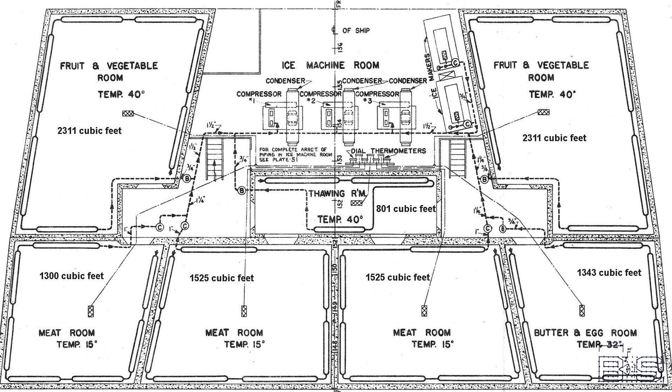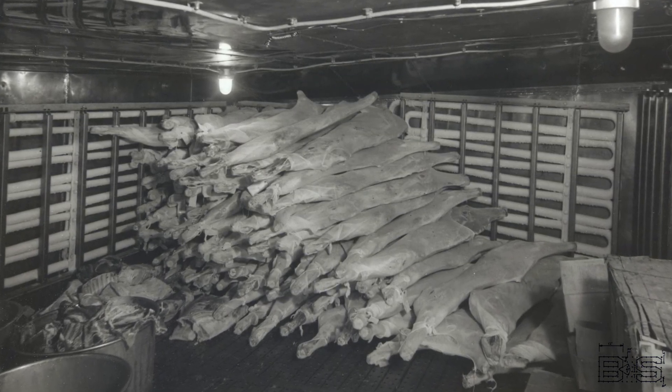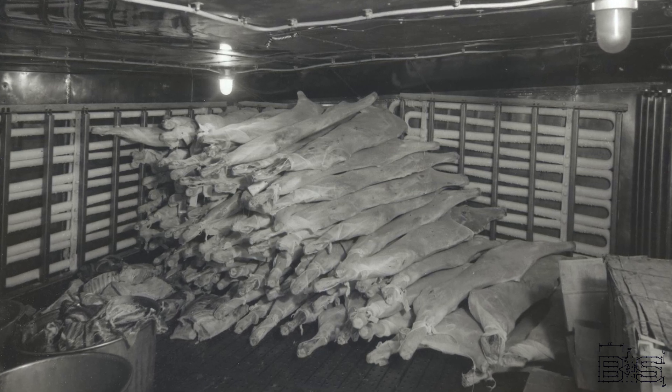The meat compartment pipes might be around negative 5 degrees, which will eventually cause ice to form. The manual recommends a couple ways of defrosting the coils: one is to shut off the supply of refrigerant and leave the door open until it defrosts, though this presents the obvious problem of thawing out your food. Another way is to steam the frost off with a steam hose. Have you ever had a refrigerator or freezer that was not self-defrosting? What did you use to get the ice off? Let me know in the comment section below and don't forget to like and subscribe.